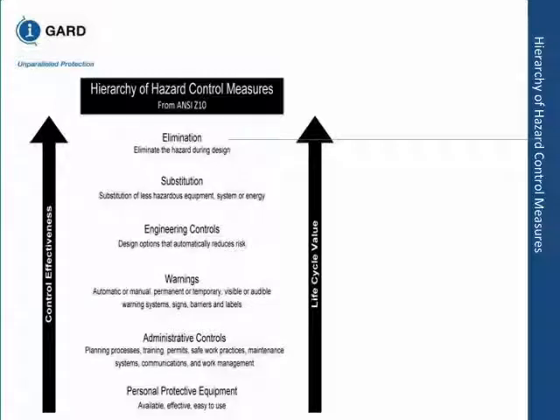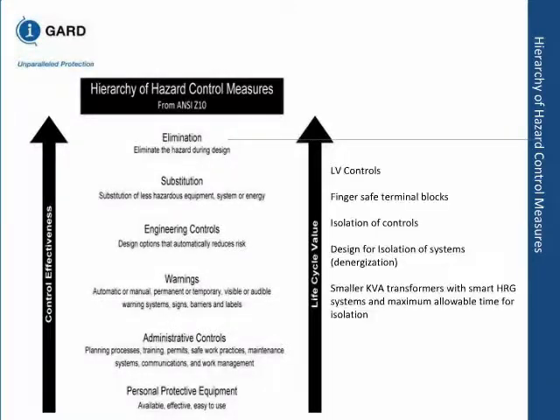Now, what are some of the methods? Let's look at that. We'll spend a little time. How do you eliminate during design? You put in some low voltage controls. Finger-safe terminal blocks. What do they do? A majority of the incidents start when somebody is working on it and they get a shock and they try to either continue, or a screwdriver hits somewhere else and causes a flash.